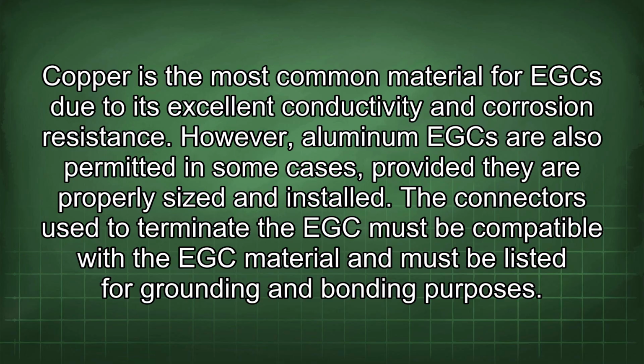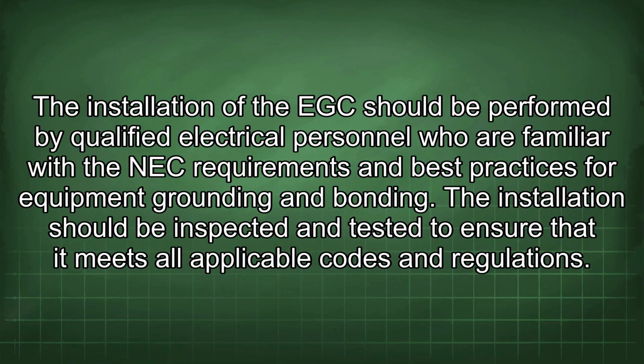However, aluminum EGC are also permitted in some cases, provided they are properly sized and installed. The connectors used to terminate the EGC must be compatible with the EGC material and must be listed for grounding and bonding purposes. The installation of the EGC should be performed by qualified electrical personnel who are familiar with the NEC requirements and best practices for equipment grounding and bonding. The installation should be inspected and tested to ensure that it meets all applicable codes and regulations.